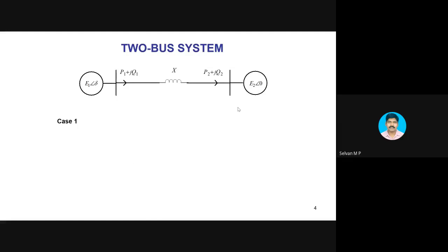Okay, so now I am considering a case study with numericals. I am considering a delta of 30 degrees, which is practically possible. And I am assuming X is equal to 1 per unit. E1, E2 are 1 per unit and 0.9 per unit. These are the conditions. I am assuming E1 I am maintaining at 1 per unit. E2 I am maintaining at 0.9 per unit. You know, per unit means say it is a percentage. If it is a 10 kV system, 0.9 per unit means it is 9 kV. If it is a 100 kV system, 0.9 per unit means 90 kV, right? This is the assumed value.